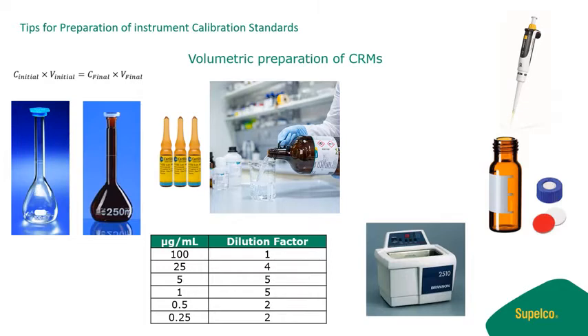Specific instructions may include storage and handling temperatures and conditions. We recommend preparing standards volumetrically or gravimetrically to ensure the highest level of accuracy and batch-to-batch consistency. Be particularly mindful that some analytes are light sensitive and their concentrations may change over time if not handled in the appropriate glassware. Some analytes may adhere via absorption to the walls of pipette tips, glassware, or sample vials. This is especially important when working at low concentration levels — PPB and below — so it's very important to follow the recommended handling conditions on the certificate of analysis.